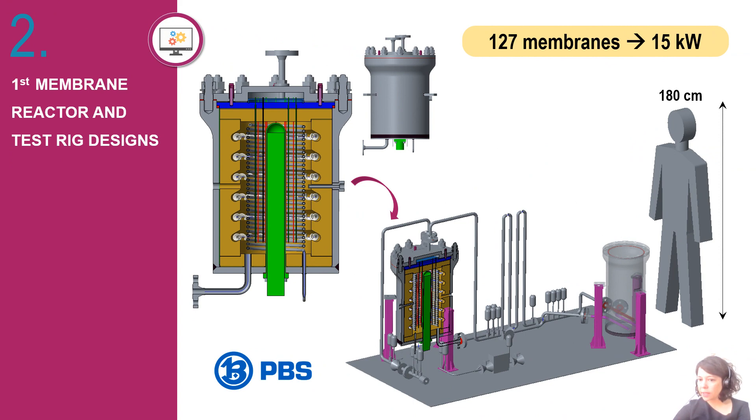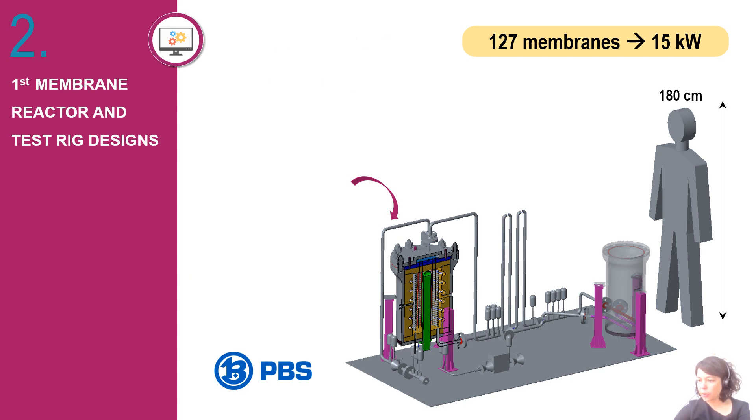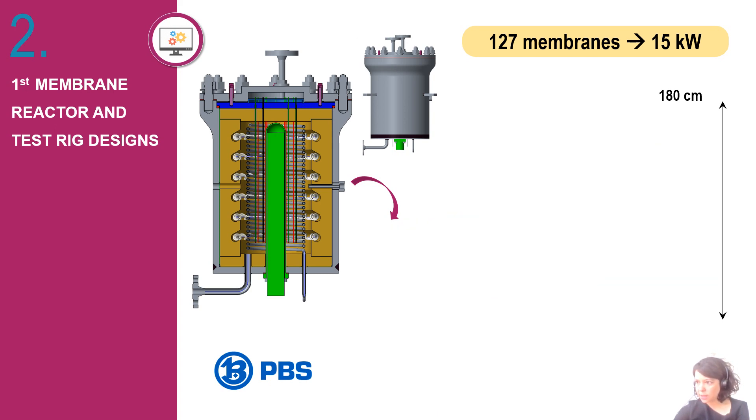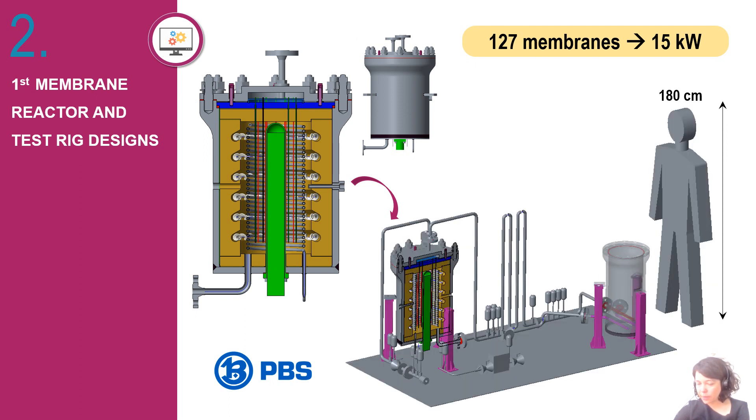This solution avoids complicated components. The membrane reactor itself consists of a steel pressure vessel with concentrically arranged membranes, insulating parts, and a heating and cooling system. Apart from the reactor, the test rig will integrate a water tank and other auxiliaries such as pumps, valves, and piping. This first proof of concept is now being optimized to produce 15 kilowatts using 127 membranes.